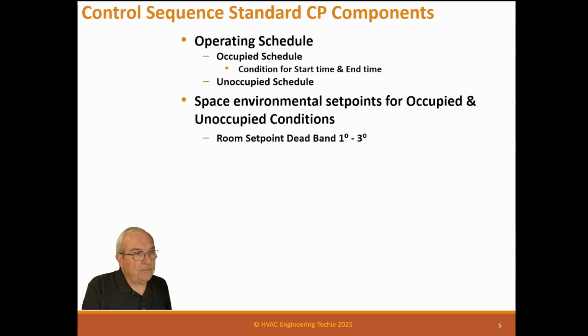Now, some LEED requirements ask for a 4-degree dead band, and that's not good. Because 1 degree, as a human being, you really can't feel. You think you can, or you pretend you can, but in reality, you cannot tell the difference. But 4 degrees, everyone can tell the difference. So if you use a 4-degree dead band, everybody's going to be unhappy about their space because it's going to get too hot before the air conditioning turns on. Then it'll get too cold, and then too hot. 4 degrees is too much.